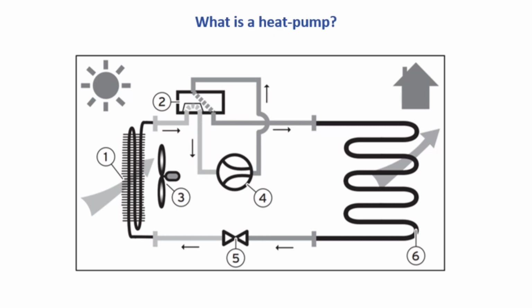And we can see here we've got a fan which blows air across a radiator. This is the evaporator, and the refrigerant flows through this radiator as it's being warmed by the surrounding air, and then it goes into the compressor. Now, what's interesting here is we've got a reversing valve, which I'll come back to in a moment. But if we ignore this for a moment, the refrigerant under normal circumstances will just go through the compressor into this condenser, which is a heat exchanger, typically coupled to a plate heat exchanger, which gets hot, and we flow water through this to the system loop, which can heat the cylinder, the various zones throughout the house, and the radiators or the underfloor heating. And the refrigerant goes into an expansion valve, and when this expansion valve releases and the refrigerant comes out cooled into the expansion radiator here and round again.